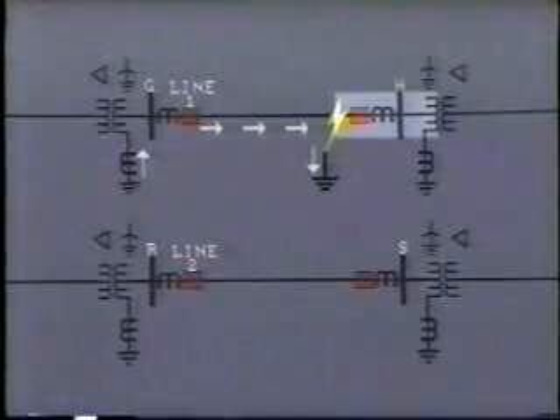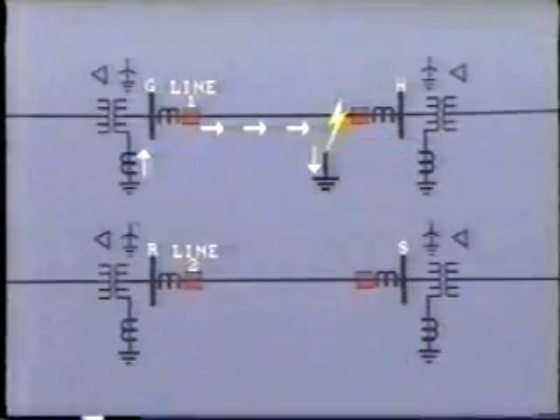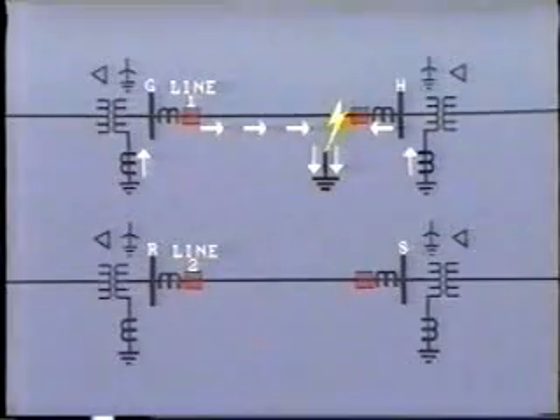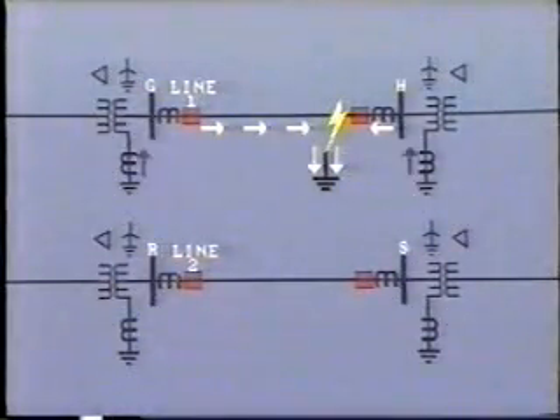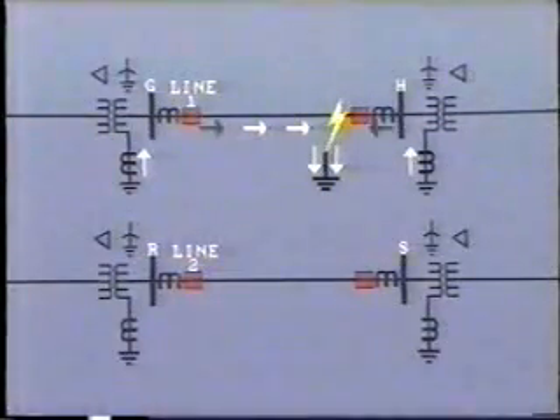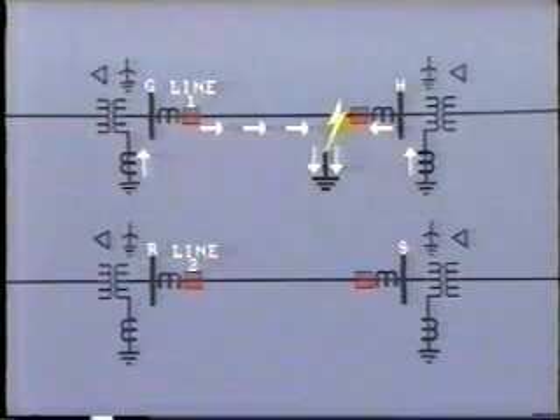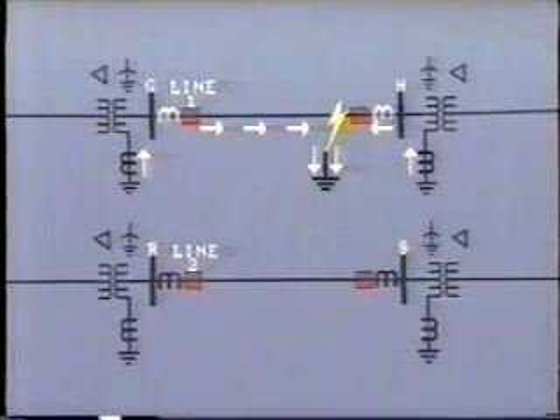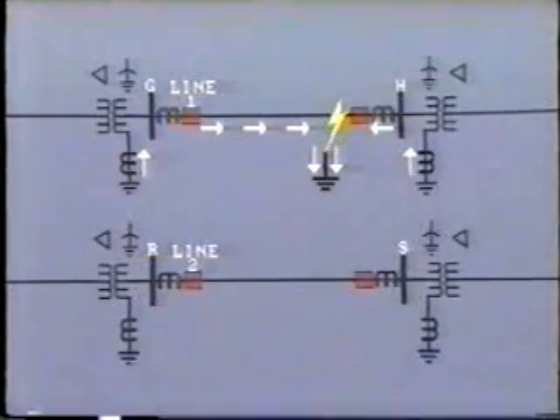Similarly, at the other end, even though the distance is short, the fault current will flow from bus H into the line, down through the fault to ground, then up the transformer neutral to bus H. In both cases, the polarizing current in the neutral and the overcurrent feeding into the line is in the tripping direction. The directional overcurrent ground relays at G and H will trip the breakers at either end of line 1 and so clear the fault.